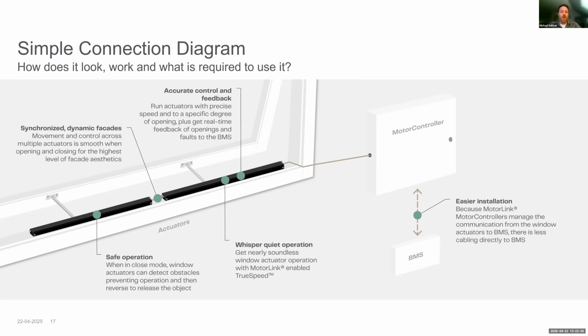The accurate control and feedback, which is also presented from the actuator, sending the signal back to the motor controller saying this zone on this window is having an error, and then that can be communicated between the controllers and the BMS system. And again, the whisper quiet operation is the TrueSpeed. It's actually called true speed with the MotorLink technology, where you can have it almost silent. It's a little whisper, but it's not affecting the occupants within the building with loud grinding, anything like that, if the installation is done correctly.